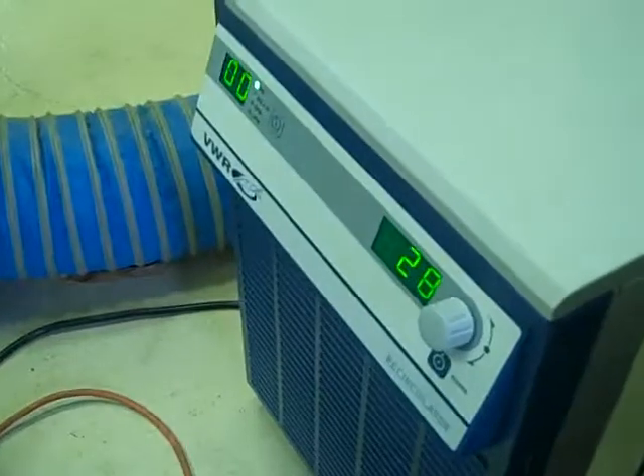First thing we want to do is turn on the circuit breaker for the chiller. Circuit breaker's on the back of the chiller. Circuit breaker on. Okay, so now that we have power, we want to hit the power button. That'll turn on the chiller.